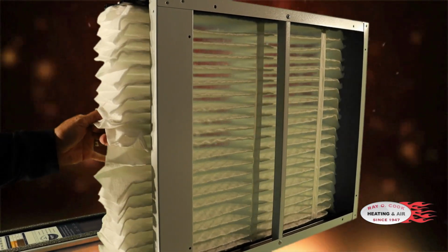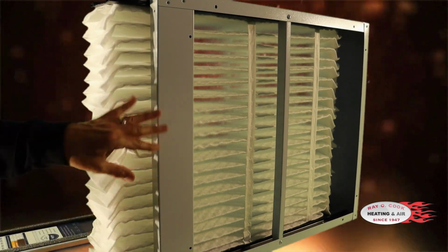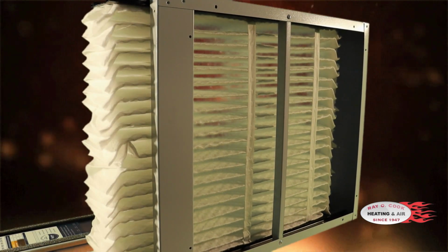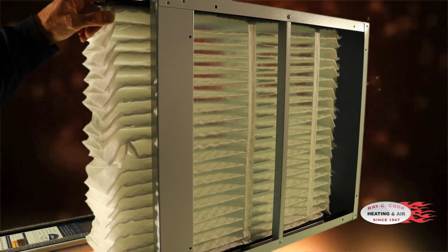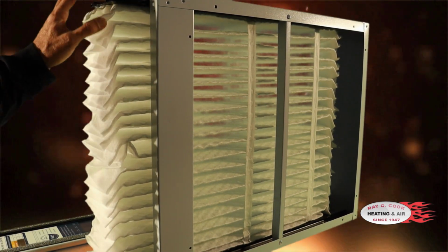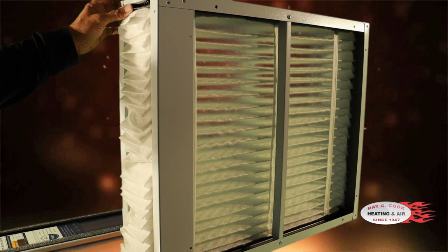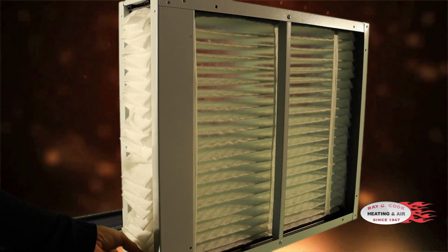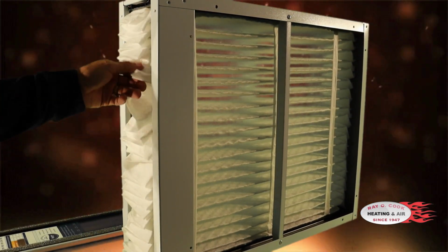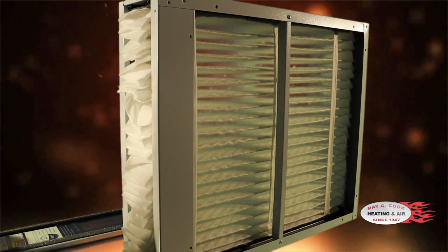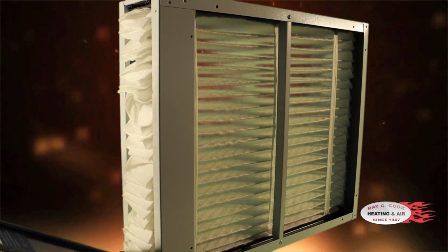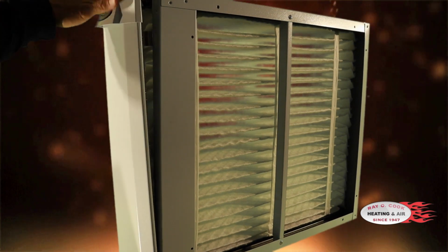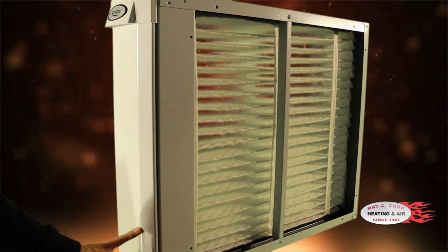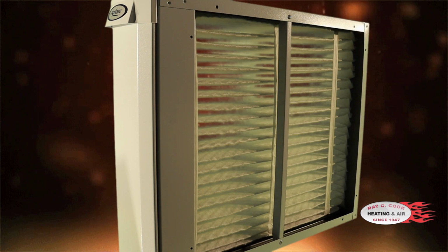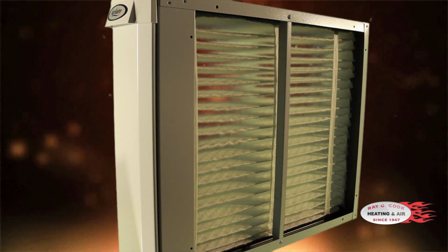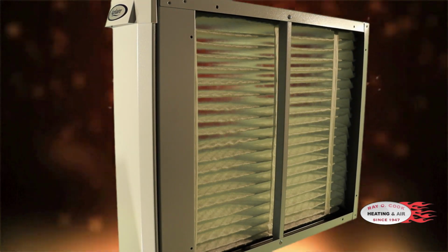This media simply slides out. You can see just how much surface area is in that media. It's dovetailed here at the top, so when you slide it in, it seals, and it's 100% bypass proof. The media, you can see, is cut long, so when you put the door on, there's no bypass on the door. And the door has a nice gasket all the way around it. Just a great product all the way around, and that's why we use it on our new installations.